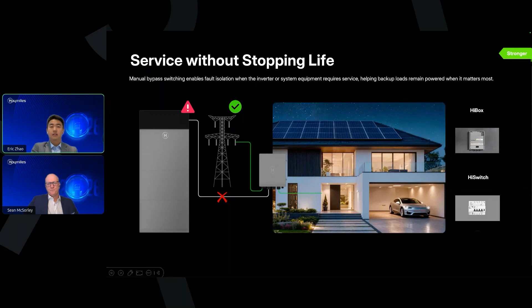When the inverter or other system equipment requires service, the bypass function allows the installer to isolate the relevant part of the system. That makes fault isolation and maintenance more convenient. Importantly, the bypass architecture helps keep household loads supplied while service is being performed, where system conditions allow, so installers don't have to treat the complete home electrical system as one single block.